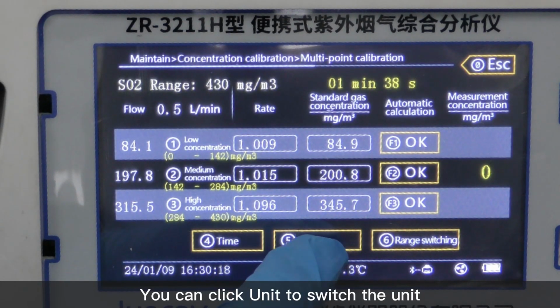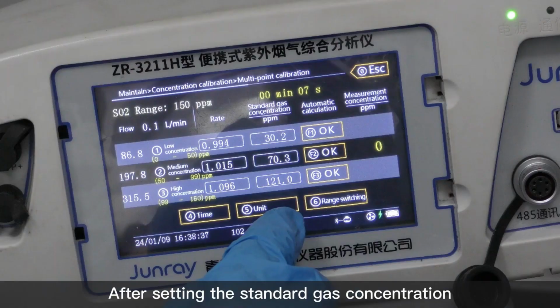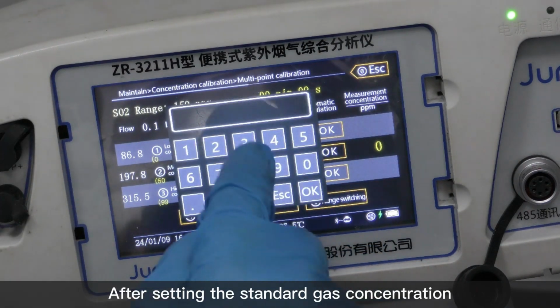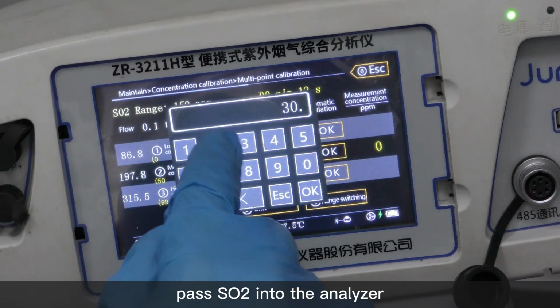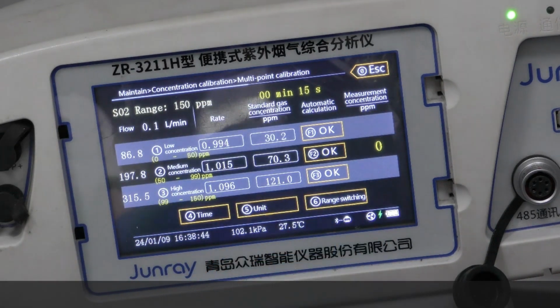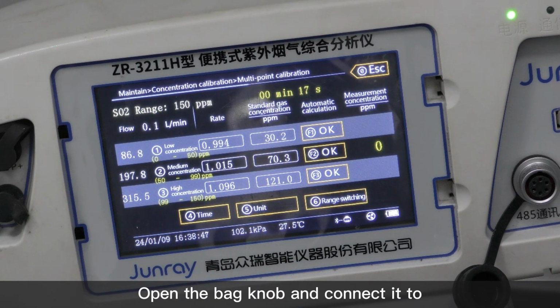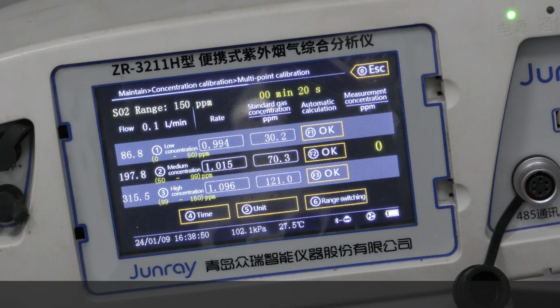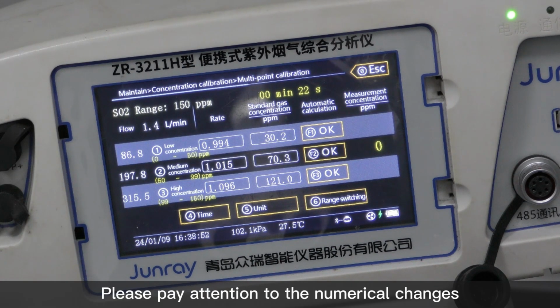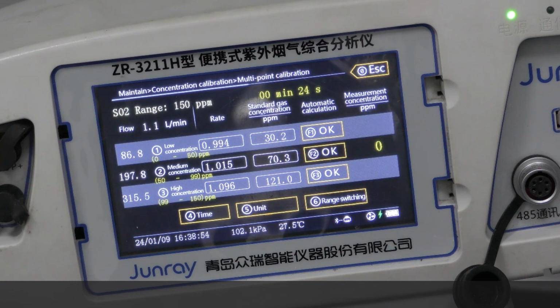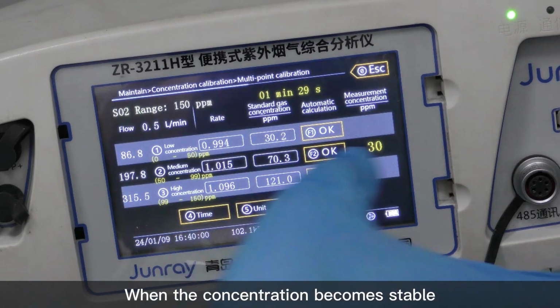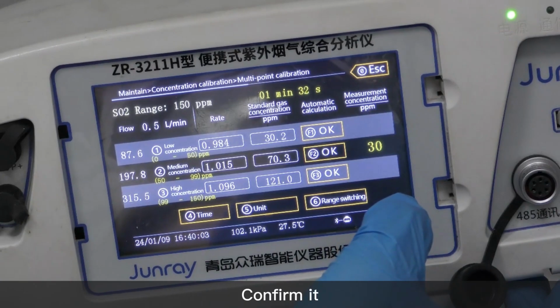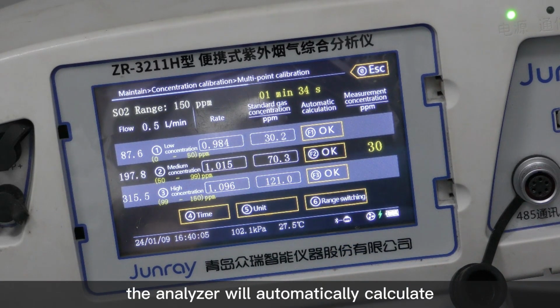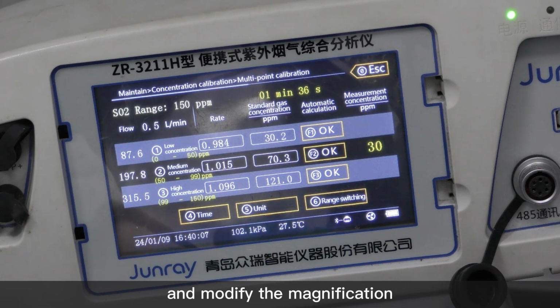You can click Unit to switch the unit. After setting the standard gas concentration, pass SO2 into the analyzer. Open the bag knob and connect it to the air inlet of the host. Please pay attention to the numerical changes in concentration at this time. When the concentration becomes stable, confirm it. The analyzer will automatically calculate and modify the magnification.